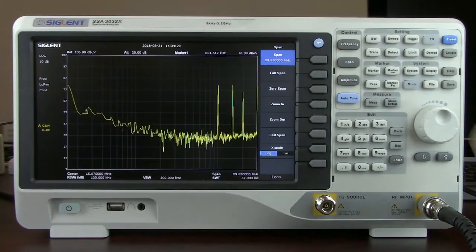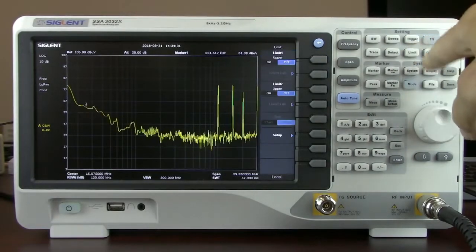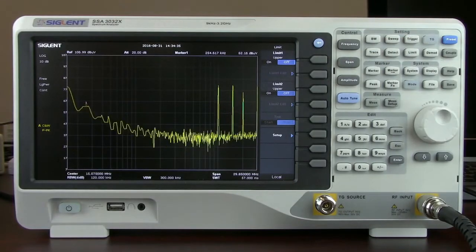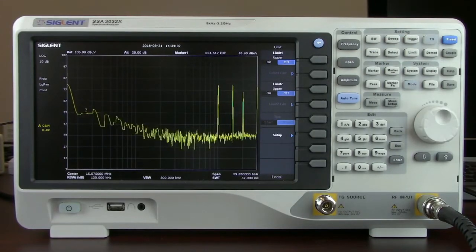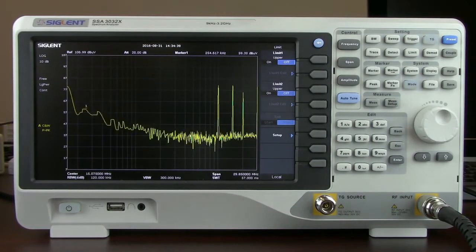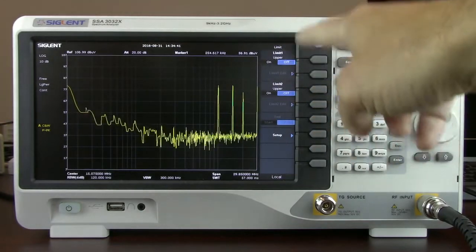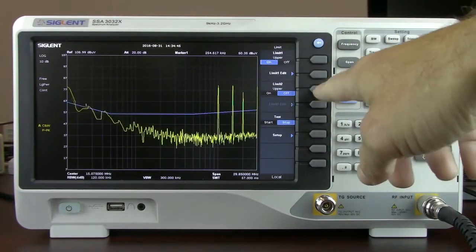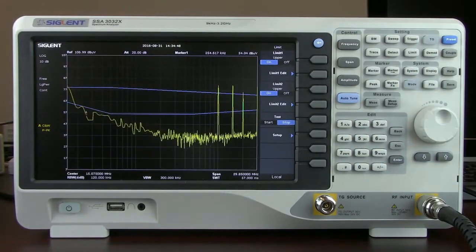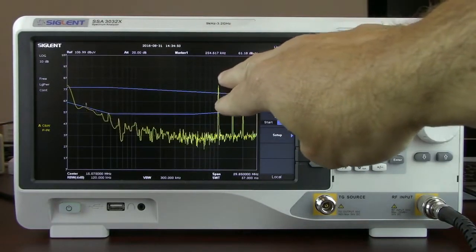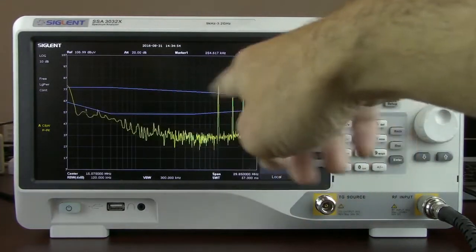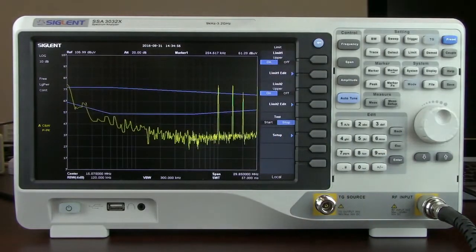And now we can enable limits. Pressing the limit key, we've got two limit lines. Many spectrum analyzers will not have two full limit lines. They'll have an upper and a lower. In this case, we've got two limit lines that we can select to be upper or lower. In this case, we're just going to turn on limit line 1 and turn on limit line 2. Now we can visualize the two limit lines that we need to meet or we may need to meet for this particular application. And then our electromagnetic performance of our device under test shown under the yellow trace here.